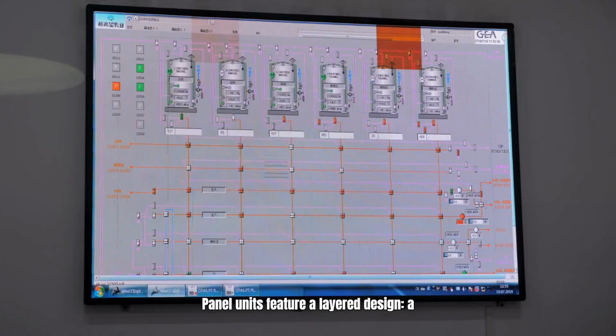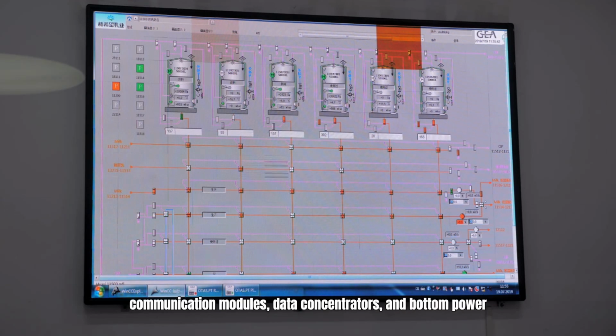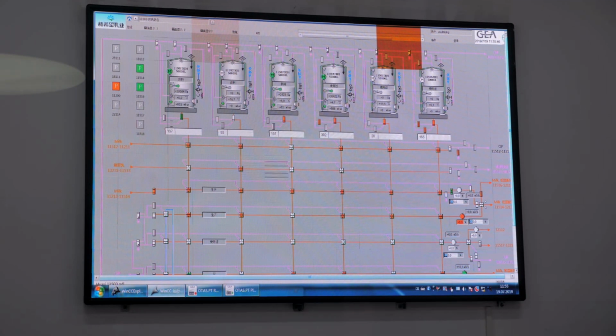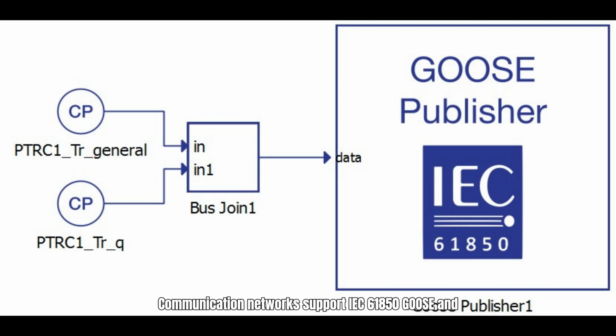Panel units feature a layered design, a top visualization HMI with 22-inch touchscreens, middle communication modules, data concentrators, and bottom power distribution units. Communication networks support IEC 61850 GOOSE and SV protocols for sub-millisecond latency, DNP3 for SCADA integration, and TCP/IP Ethernet for wide-area networks up to 10 gigabits per second.